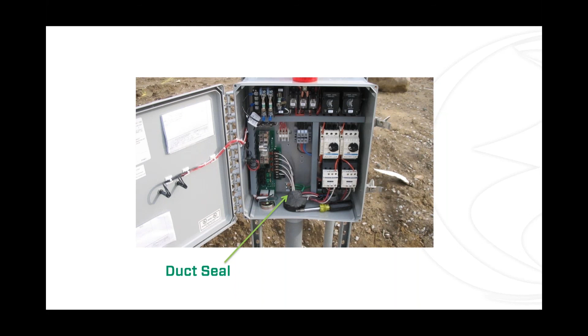Spray foam does a great job of sealing up the conduit, but the problem is you can't get your wires out when you have to replace something in the future. Spray foam in a conduit can be an absolute nightmare to remove. Sometimes you can't, and you just have to cut everything out and start over, which is a really expensive, silly mistake to make. So use duct seal instead. Here's an example of duct seal packed around the incoming wires of this control panel.